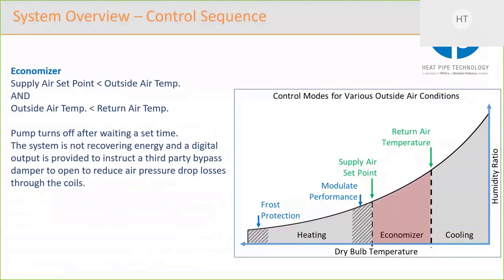This is another element where we have a dry contact output. So for those people who don't have a building automation system, you could use that output, for example, to activate a bypass damper so that during those economizer hours, you're not having to pay for the pressure drop across the coils. You can actually bypass those and save some energy.